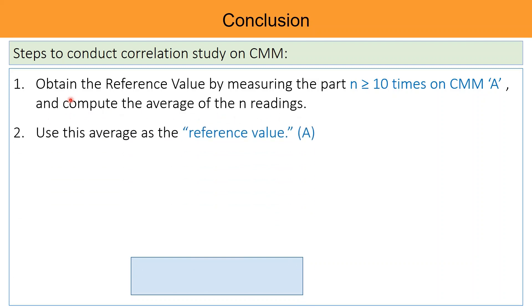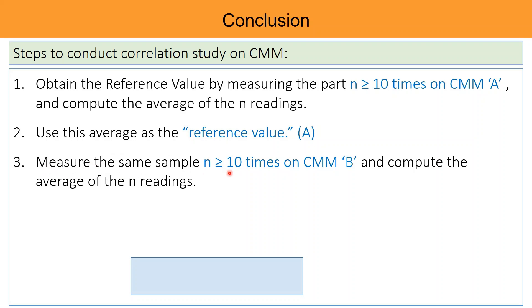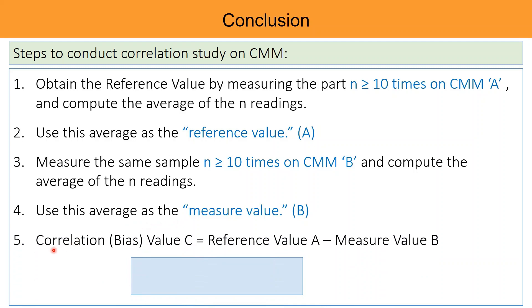Steps to conduct a correlation study on CMM: Obtain the reference value by measuring the part more than 10 times on CMM A and compute the average of the n readings — use this average as reference value A. Measure the same sample more than 10 times on another CMM B and compute the average of the n readings — use this average as measured value B. The correlation or bias C is equal to reference value A minus measure value B. So C = A − B is the bias between the two measuring machines.